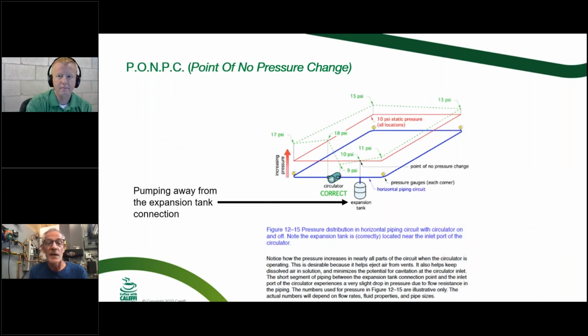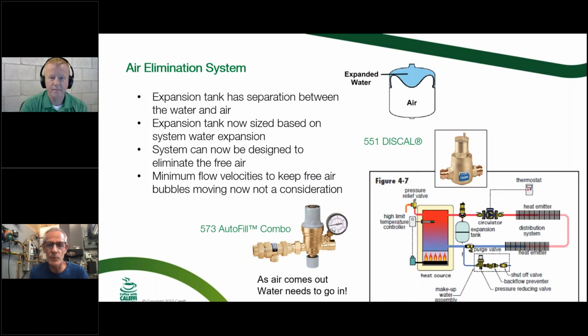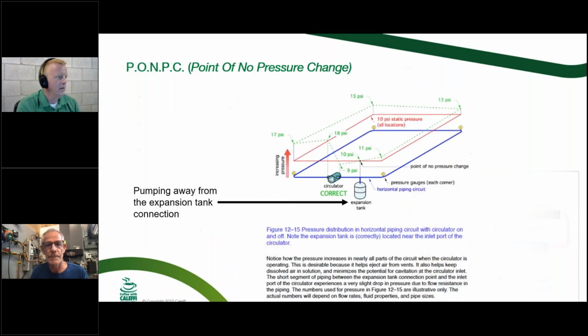Yeah. And then the last point there on that slide, Cody, if you give me a second, is sometimes people oversize the piping, and I'm working with a guy right now in one of the chat rooms who wants to pipe his boiler with 1.25 inch pipe, even though he barely needs 1 inch pipe. I said, well, you're going to slow down the velocity. If you slow down the velocity, these camel type air scoops don't do a very good job of pulling the air out. Now the micro bubblers like the Discal will work down even at 2 feet per second velocity. So that's the difference between just using a wide spot in the road as opposed to having something that has a mesh or medium to grab bubbles at slow velocities and also the smallest bubble possible. So, for sure. Okay.